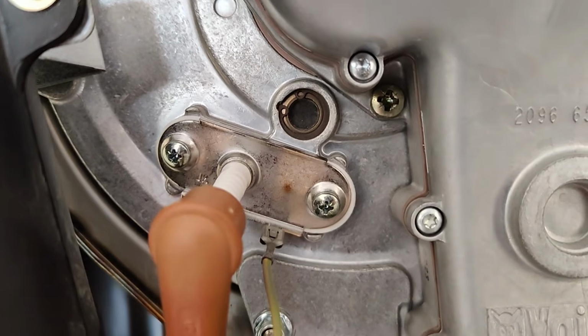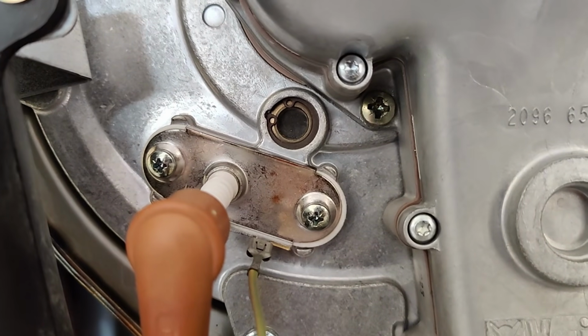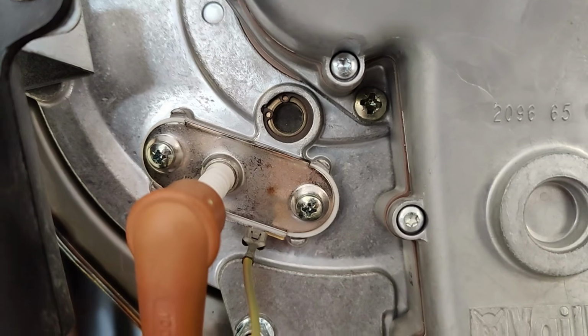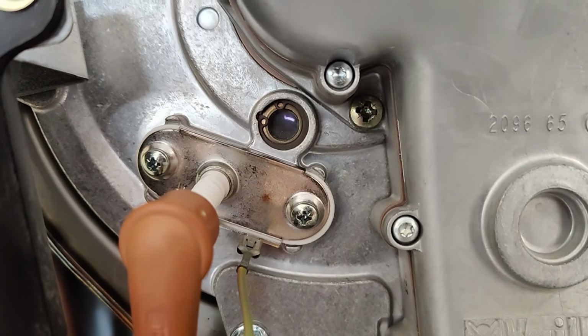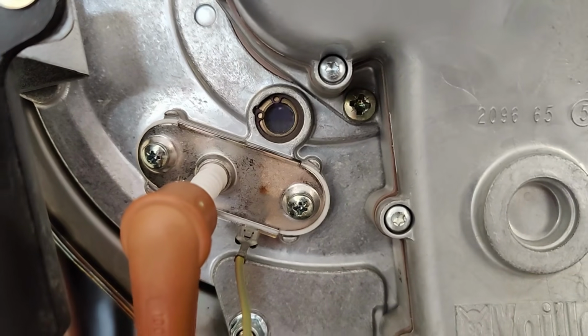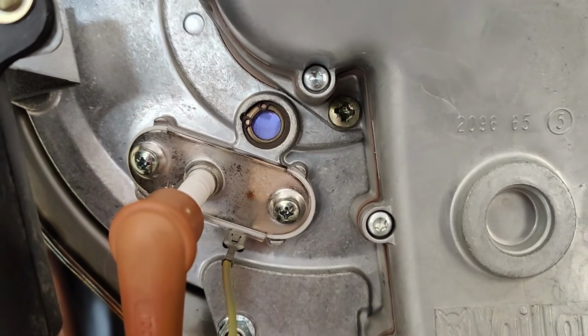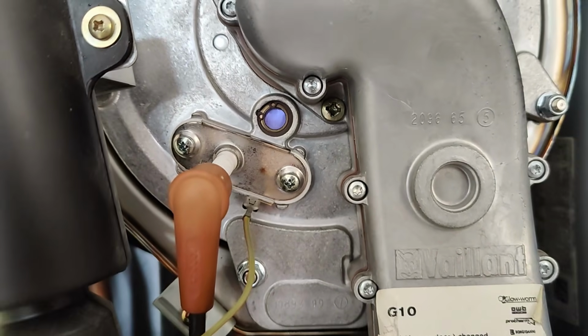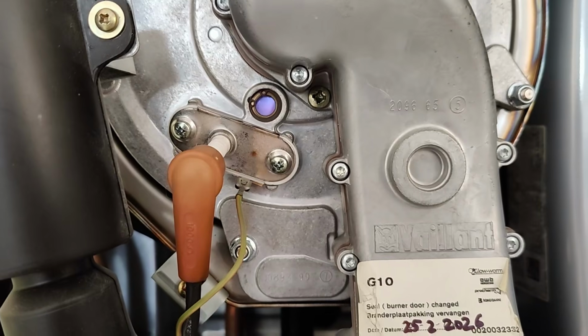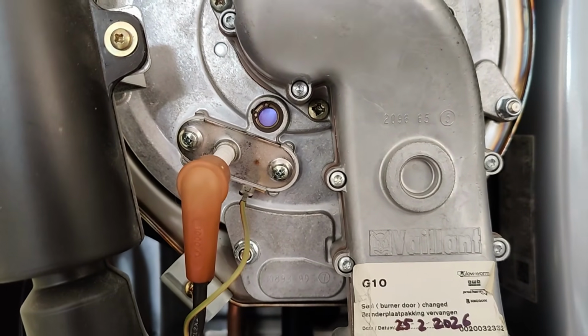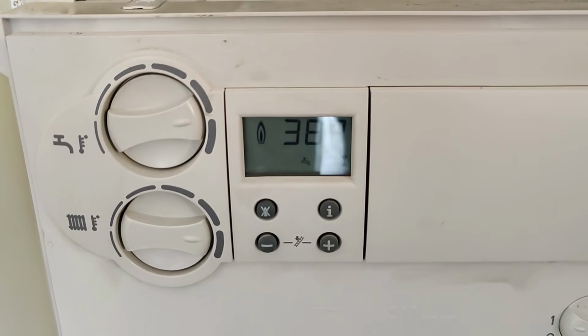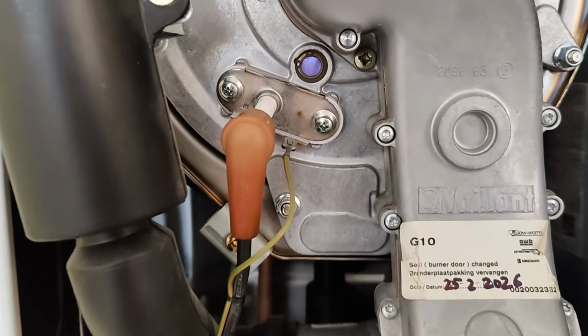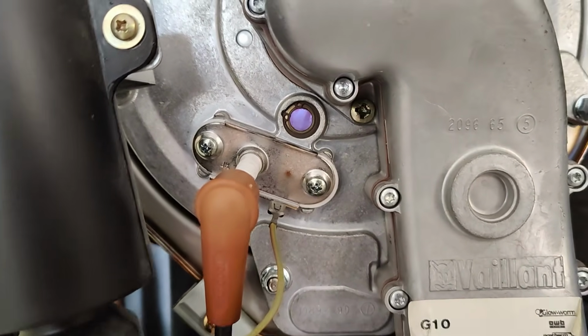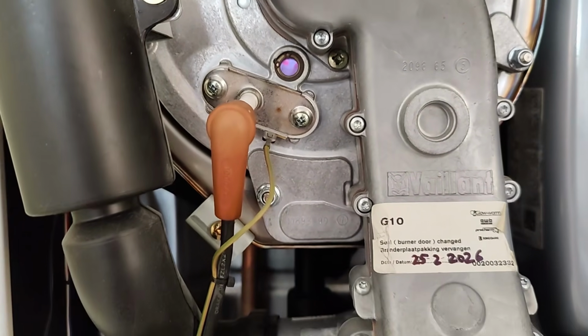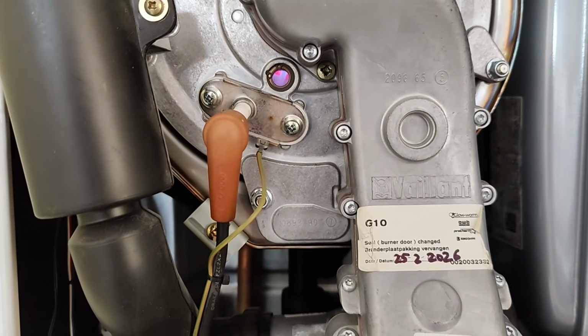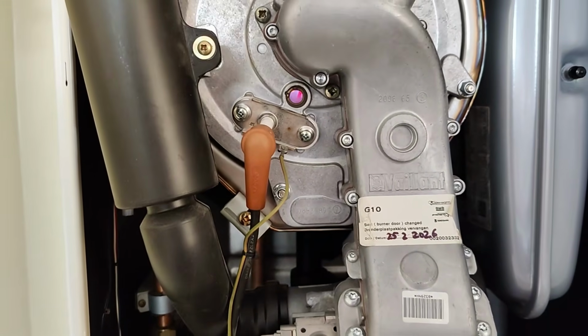Okay, so I've just created demand. There we go. So we've got hot water running. Let's see what the boiler does now. You can see it's igniting. There you go. It seems like the gas valve's sticking. It's most likely the gas valve's not allowing enough gas to pass through. So now it's got flame on, but it did struggle, as you saw. So it seems like it's not necessarily the PCB issue or the lead, it's most likely the gas valve. But let's do some testing, let's figure it out.